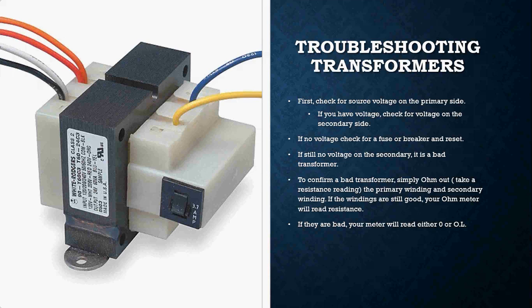When it comes to troubleshooting a transformer, they are relatively simple components to troubleshoot. The first thing you're going to want to do is make sure that you have power going to the primary side of the transformer. The primary side is on this side here — as shown in this picture.